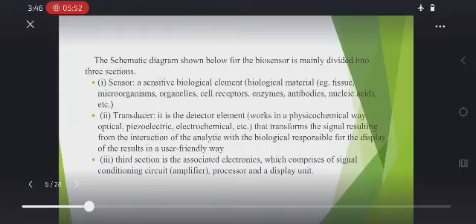Next is the transducer. The transducer is the detector element that works in a physiochemical way, optical, piezoelectric and electrochemical, that transforms the signal resulting from the interaction of the analyte with the biological element, responsible for the display of the result in a user-friendly way. The third section is associated with the electronics, which comprises a signal conditioning circuit. What is the signal conditioning circuit? It acts as the amplifier. What is an amplifier? An amplifier amplifies the signal, along with the processor and the display unit.